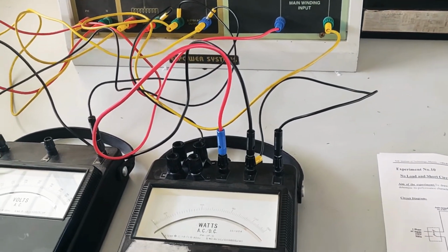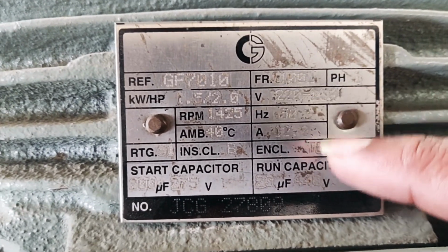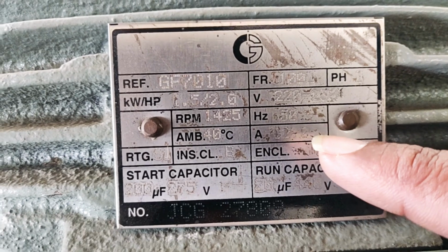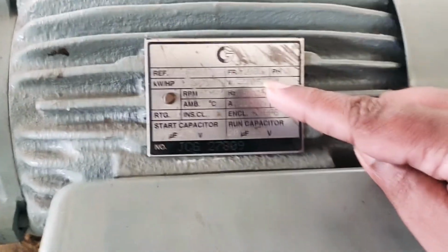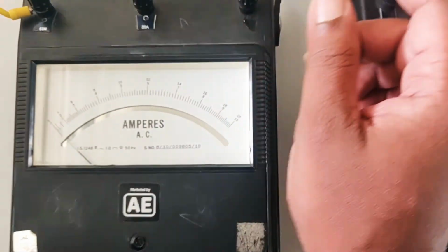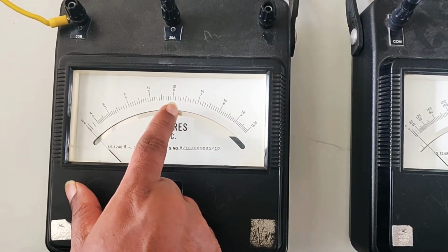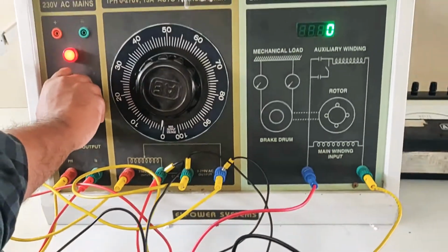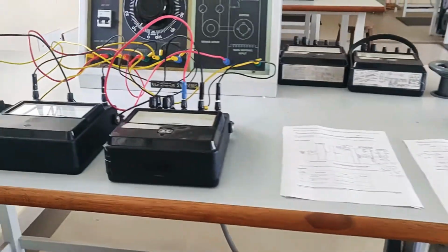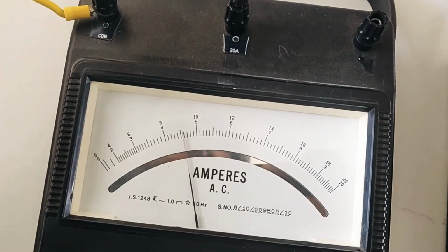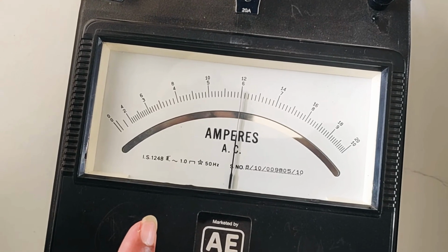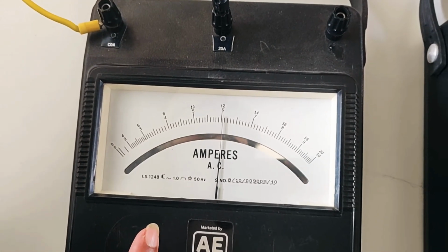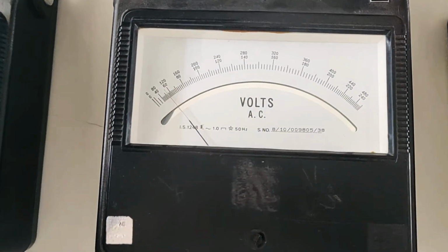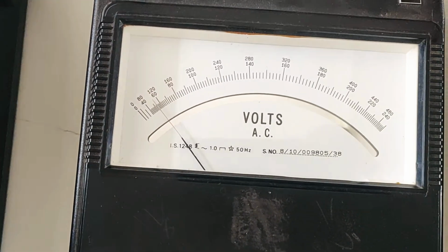The rated current of the induction motor, you can see from the nameplate details, is around 12 amps. In the SC test we have to apply 12 amps by applying a certain voltage, which will be 20 to 50% of the rated voltage. You have to vary the auto transformer until this ammeter indicates 12 amperes. Firstly I will switch on the MCB, and then I will apply voltage such that this ammeter indicates 12 amperes. It is approximately 12 amperes.